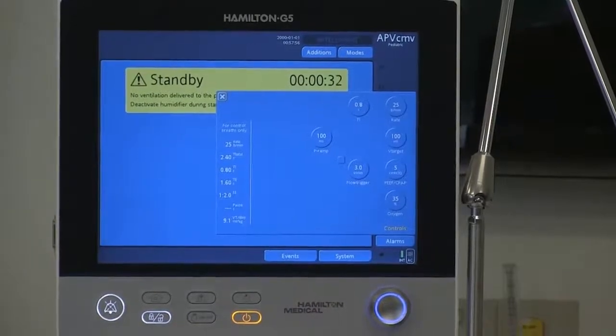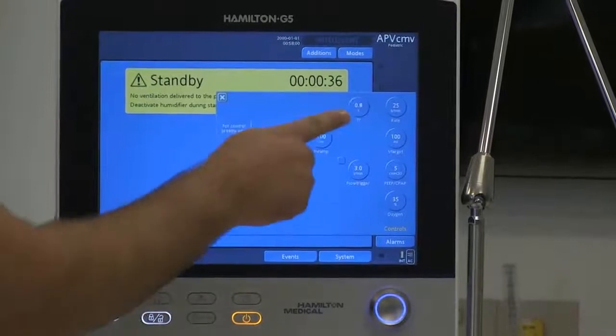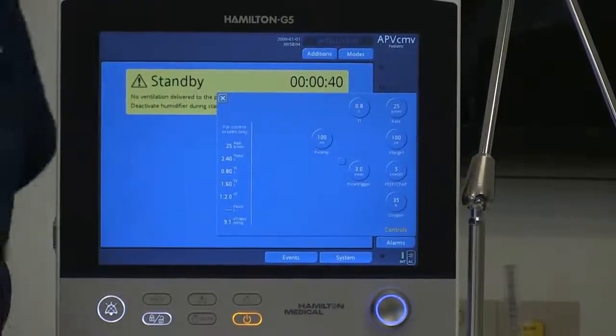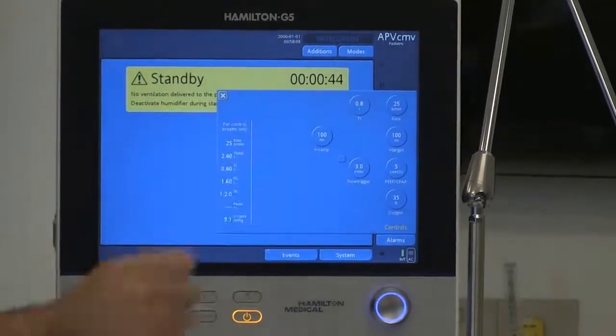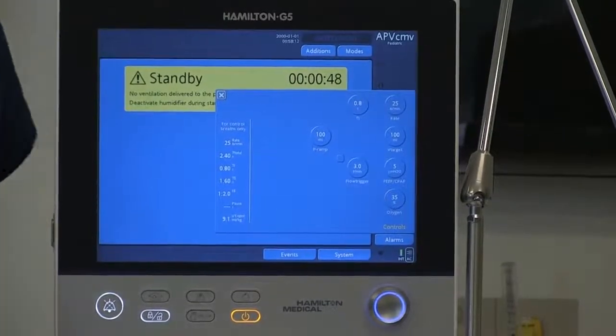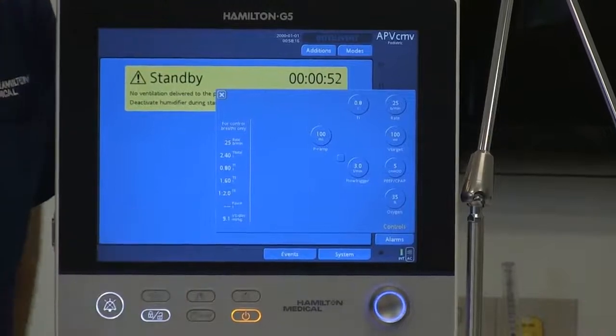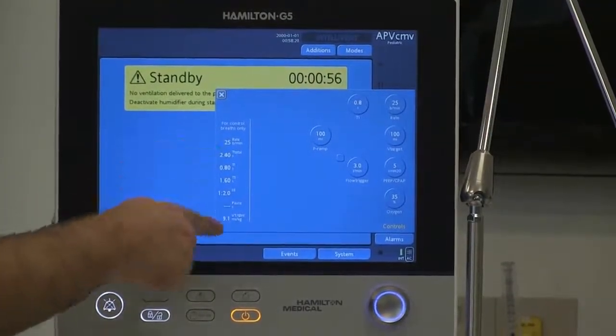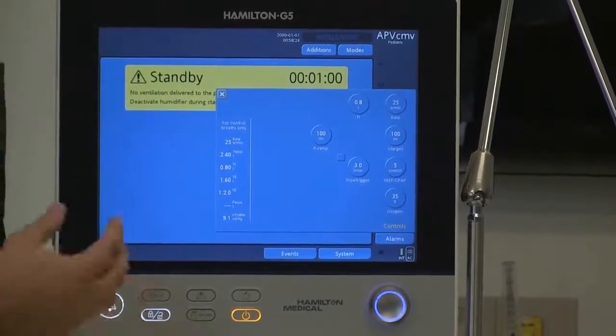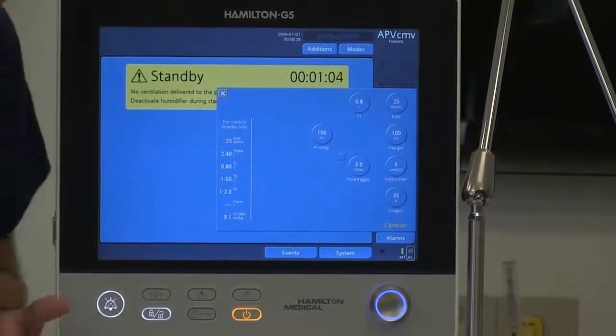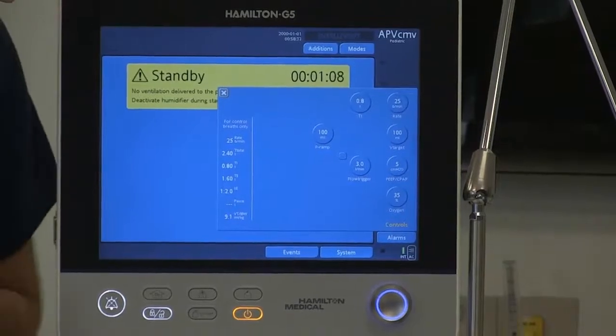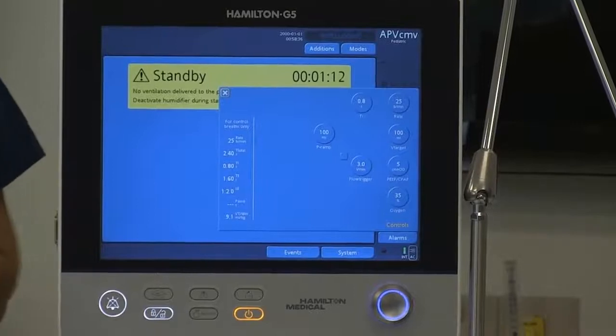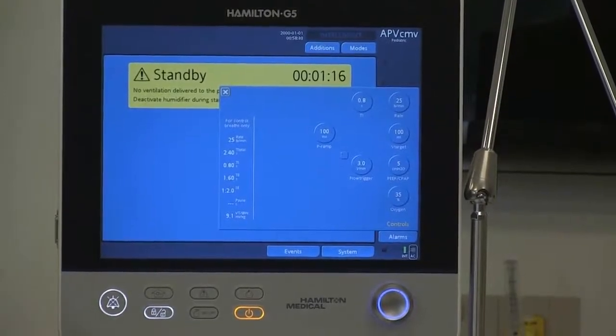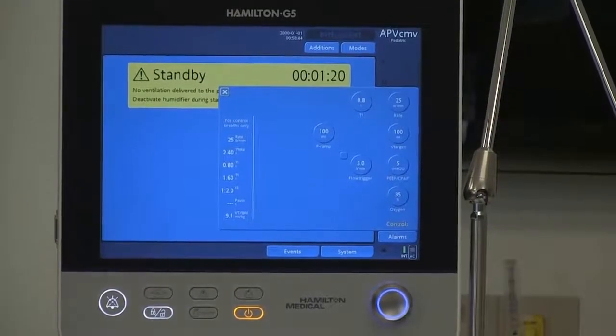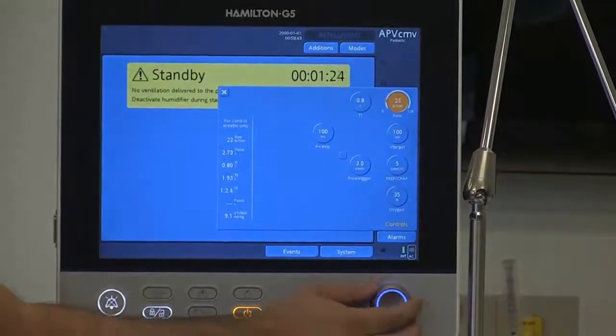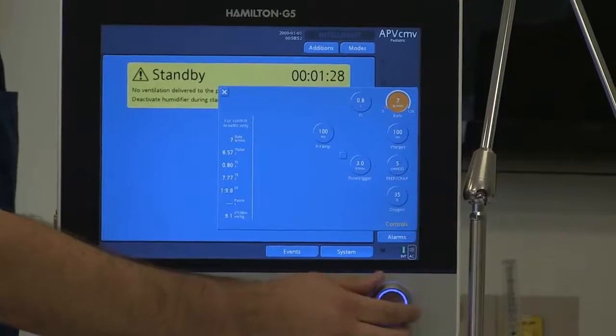Up here, you'll have all of your general ventilator settings: I time, rate, target volume, since we are in adaptive pressure ventilation, P ramp, which is akin to rise time, flow trigger, PEEP, and FiO2. Also over here, you'll find a calculator window, which will change and give you calculated values such as rate, total cycle time, I time, E time, I to E ratio, and if you have the accurate ideal body weight plugged in, it will give you your tidal volume per kilogram of ideal body weight. If you notice, when I start to change the rate, it also changes all the values on here even before I've confirmed.